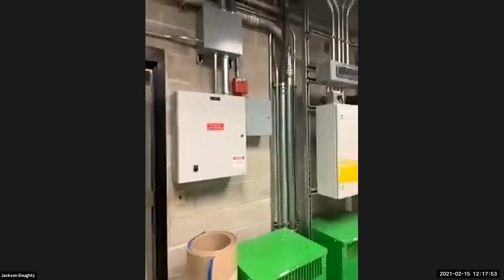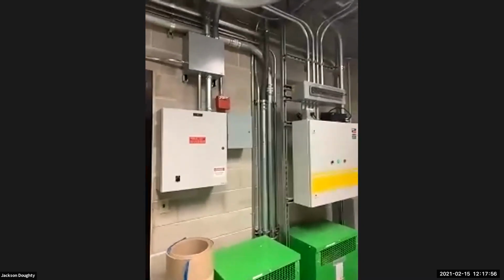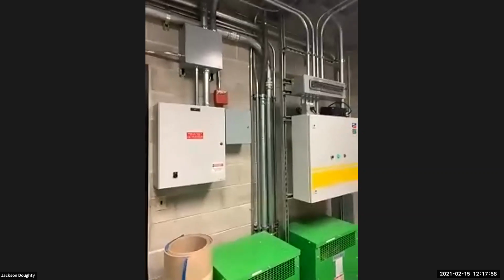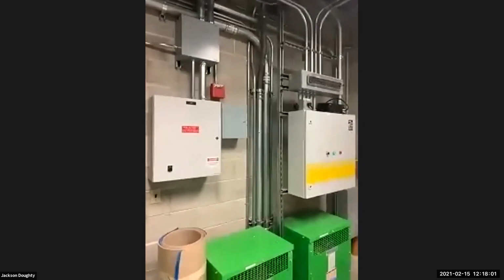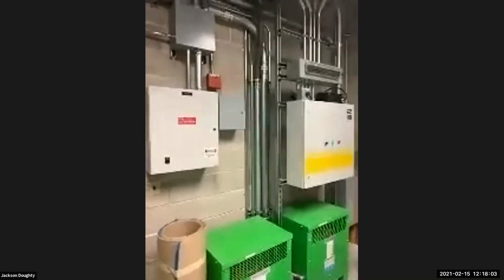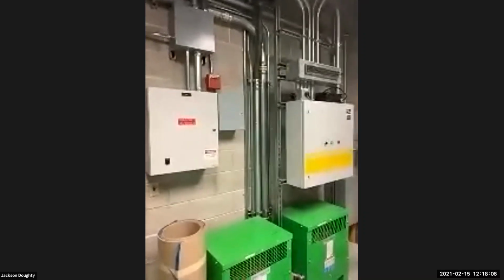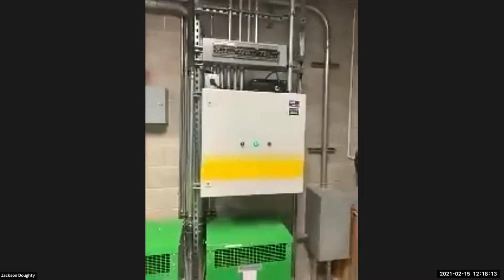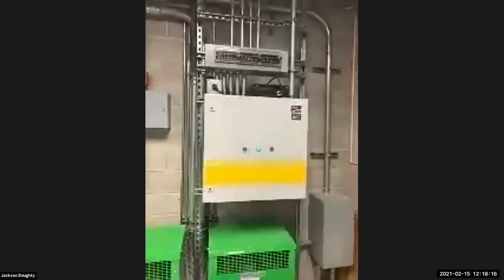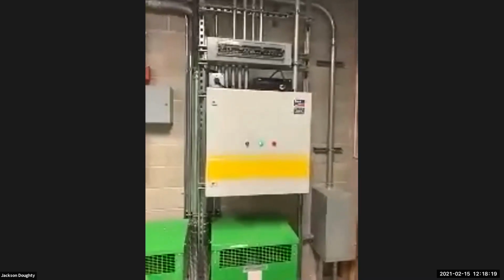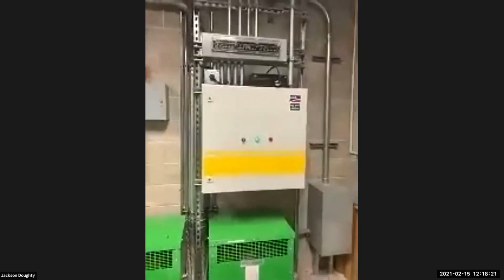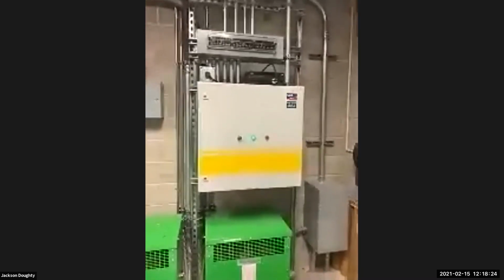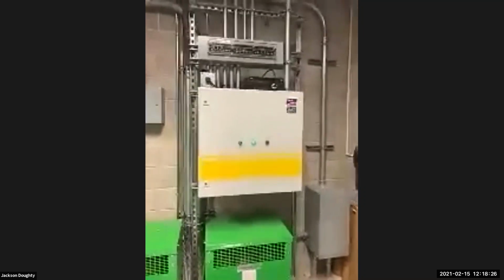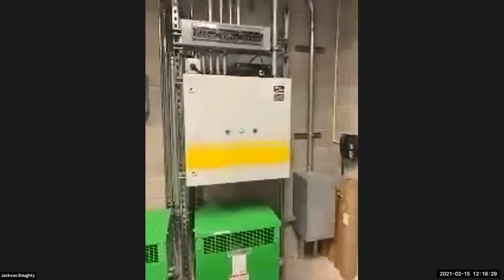But essentially what's going on in the electrical room is that this ATS is sensing for grid outages. So in the event of a grid outage, the solar PV is reconnected to serve the school's load and is monitored and controlled by the fuel saver. So the fuel saver is essentially starting up the diesel generator, but is reducing the diesel generator's load when the solar is online, so that the school in island mode is able to use the solar as opposed to the diesel.